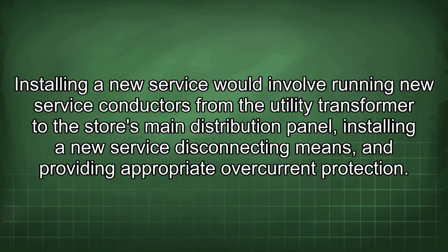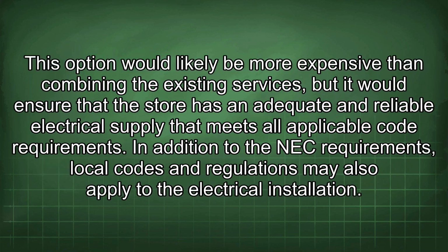Installing a new service would involve running new service conductors from the utility transformer to the store's main distribution panel, installing a new service disconnecting means, and providing appropriate overcurrent protection. This option would likely be more expensive than combining the existing services, but it would ensure that the store has an adequate and reliable electrical supply that meets all applicable code requirements.